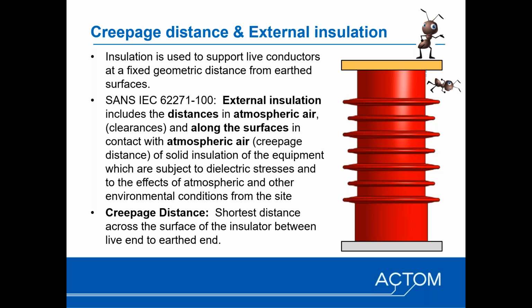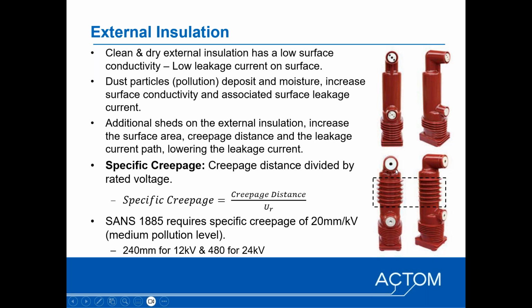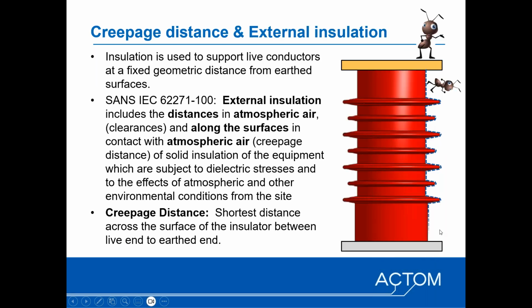Now, creepage is defined as the shortest distance from the live end to the earth end of the conductor over the surface of the insulation. And we sometimes refer to it as the lazy ant, walking across the insulation, taking the shortest distance. So that is defined as the creepage distance across the surface of the insulation. Now, because you've got a potential difference across the insulation, and you've got a surface resistance or conductivity on the surface, there would be a leakage current flowing over the surface.